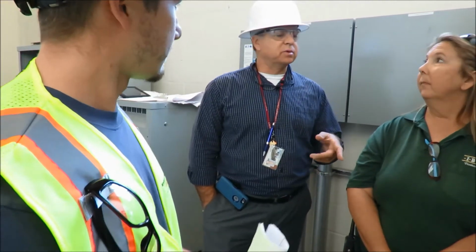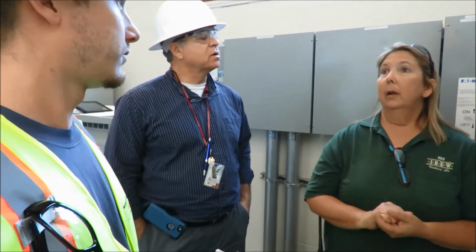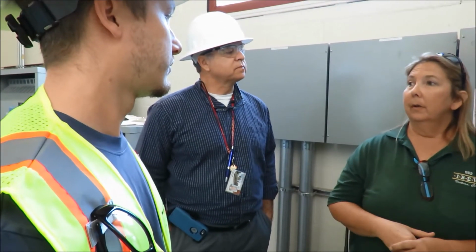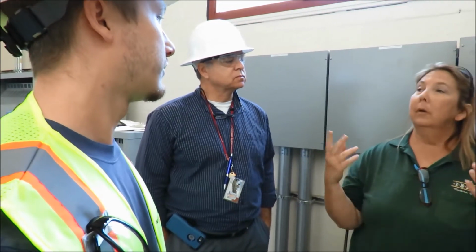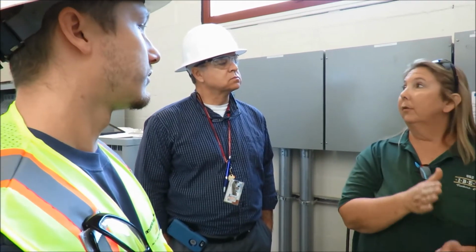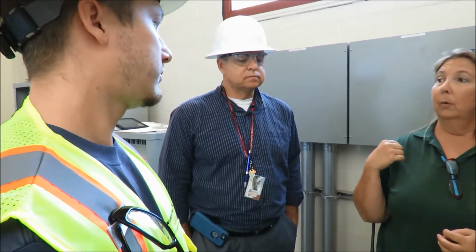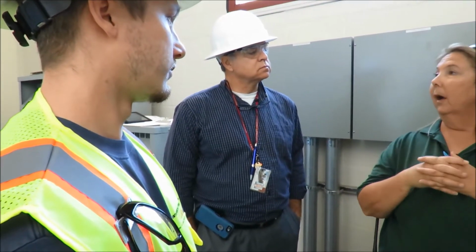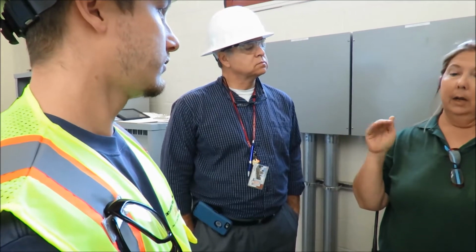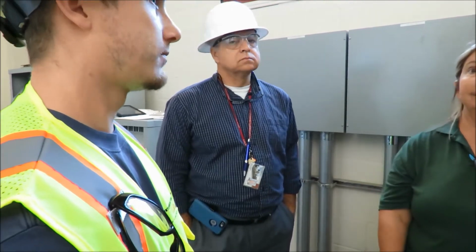The override is critical because we've been having problems. In Del Norte, the one door, there was some testing, they forgot to bypass the module, the door came down, and we don't have the ability to manually reset the door. We have to call somebody. I was told through some training that even if we have the ability to get that door back up, we still have to call them because anytime it's deployed, they have to come and calibrate.